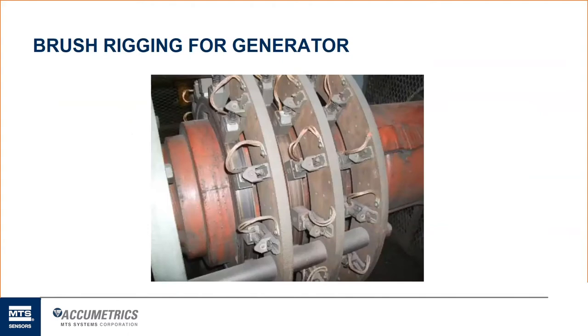So this is the brush rigging. There's two types of excitation systems for generators. You can think of the exciter as the power supply, essentially, for the generator. So the two types are brushed and brushless. In a brushed system, which is what this picture is, all of your brush rigging and your circuitry is out in the stationary world. They bring that across with this brush rigging assembly. They bring a DC power source across to that, and they contact these slip rings that are press fit onto the shaft itself. So that's how they're getting their DC power source out to the rotating shaft as the machine is spinning around.